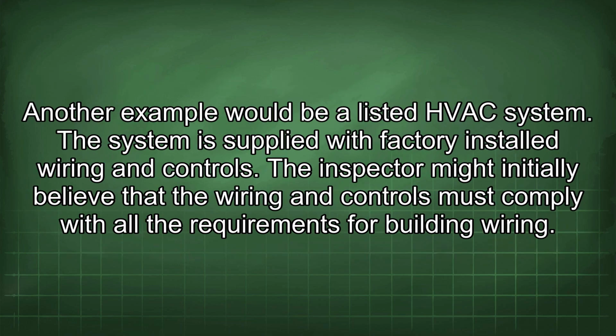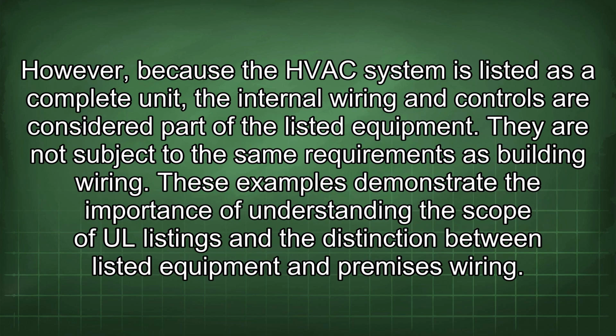Another example would be a listed HVAC system. The system is supplied with factory-installed wiring and controls. The inspector might initially believe that the wiring and controls must comply with all the requirements for building wiring. However, because the HVAC system is listed as a complete unit, the internal wiring and controls are considered part of the listed equipment. They are not subject to the same requirements as building wiring.